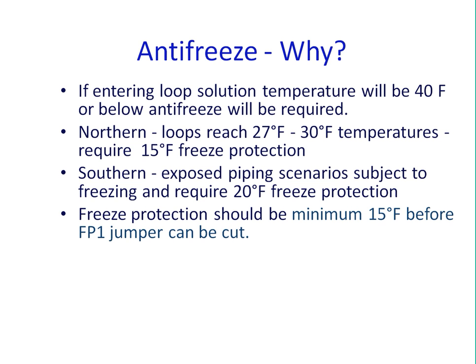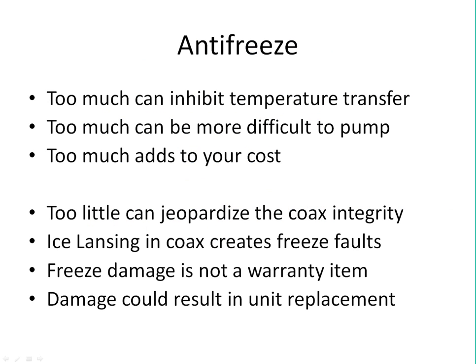Once you've achieved a minimum level of 15 degrees, if you've applied that much freeze protection into your system, then you want to go ahead and cut that FP1, also labeled as JW3 jumper. That way you can realign the circuit board to where it can now operate at a lower temperature. And I will tell you, if you forget to do that in the first couple, 3 weeks of the heating season, you're going to get a phone call from your customer that they went out on a freeze protection fault because that entering water solution entered at about 40 degrees or so, and it tripped. It assumes with that jumper not cut that you are pumping raw water through it, and its trip point again is at 40 degrees entering.